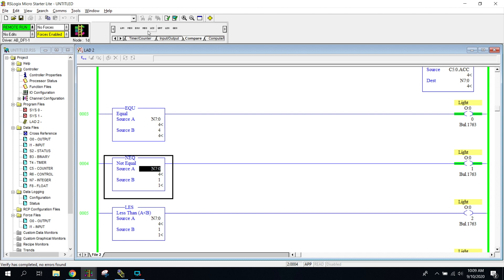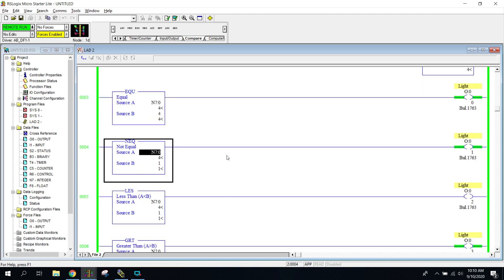This next one is a not equal instruction. Source A is four, but source B is one — they are not equal right now, so it is creating a path of true. Using the loading dock scenario, if there were only three trucks and I wanted four, we could have a red light or a siren indicating trucks are moving. As soon as A hits the value of B, the not equal rung would go false while the equal rung above would go true.